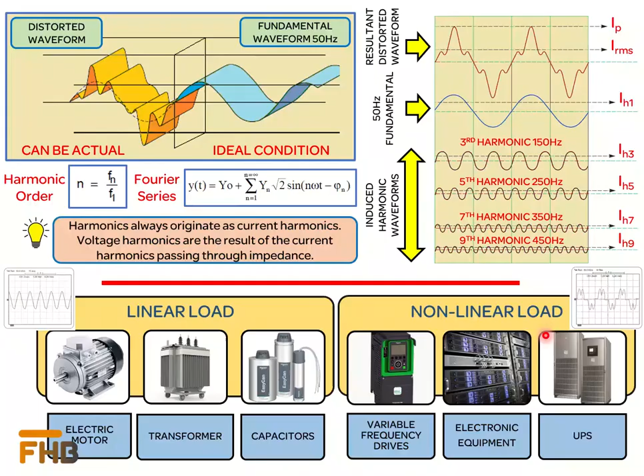To understand the effect of harmonics in the power system, we now consider a power distribution network. The incoming supply is through a distribution transformer. The network also comprises an emergency generator to ensure backup supply, and the power factor improvement plants. The nonlinear loads connected in the system inject harmonic current into the upstream distribution network. As shown here, the harmonic currents generated by different nonlinear loads are summed up at the busbar level and then passed to the connected distribution network. It is important to mention that due to different technologies of nonlinear loads, the harmonic currents even of the same order are generally not in phase with each other.